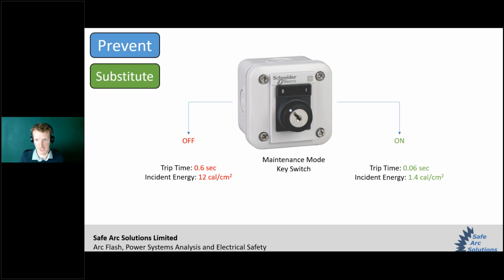So you can see in this particular example, it might go from a 0.6 second trip time in normal mode to 0.06 seconds in maintenance mode, reducing that incident energy by quite a lot. So this is quite a popular, almost retrofit option for existing switchboards.